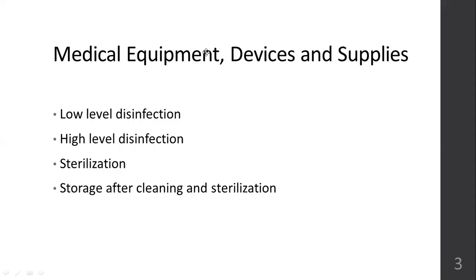Some spores can be destroyed, not all. Intermediate level disinfection is used for non-critical items that contact intact skin, but not the mucous membrane. For example, a stethoscope when doctors use it, thermometers, ECG leads. So what can you use for intermediate level disinfection? Alcohols, spirit, phenolic compounds, iodophors, sodium hypochlorite at an increased concentration, not the low concentration. Low concentration is low level disinfection. As you increase the concentration of sodium hypochlorite, that is bleach, the level of disinfection also increases.